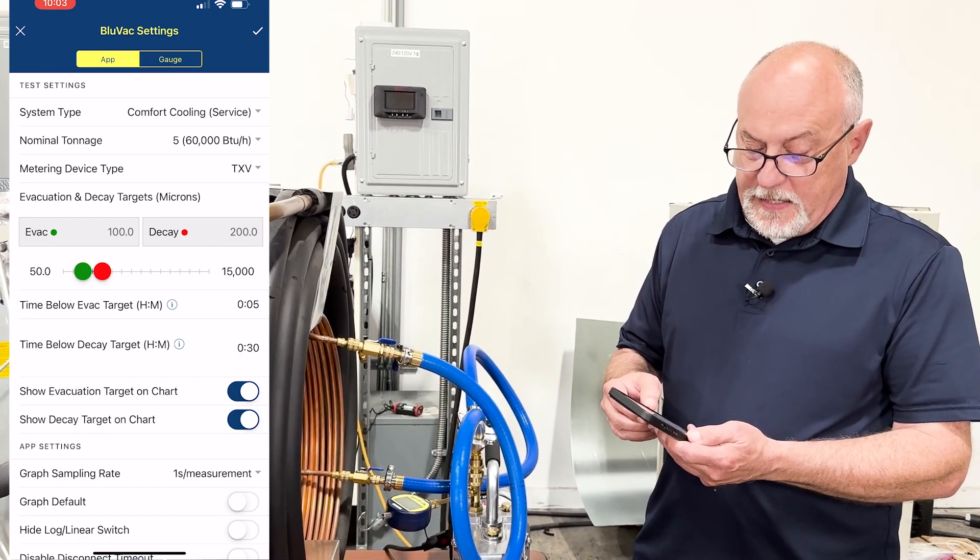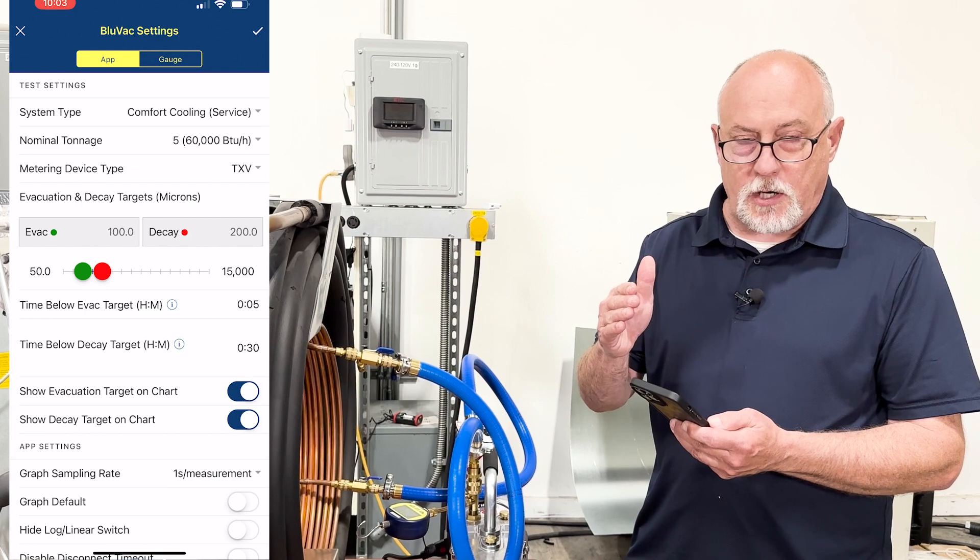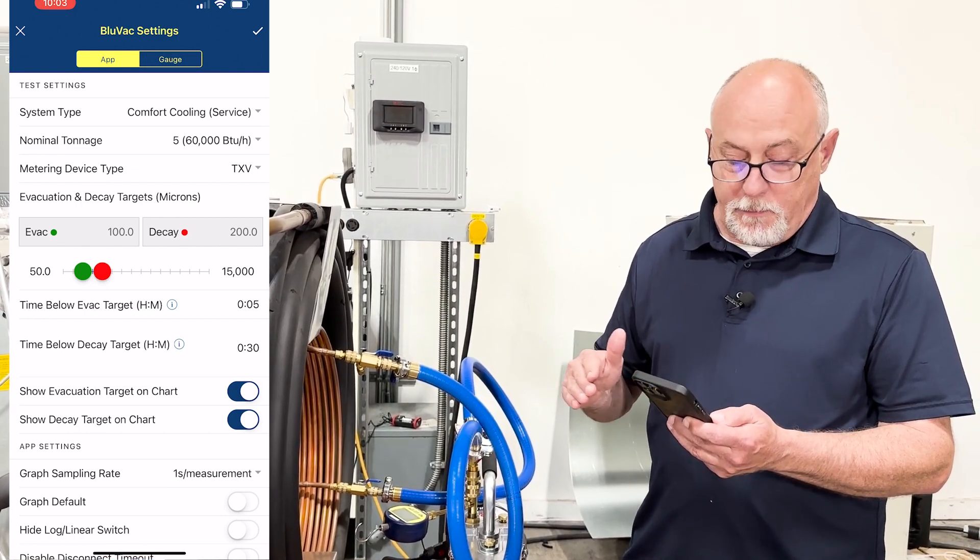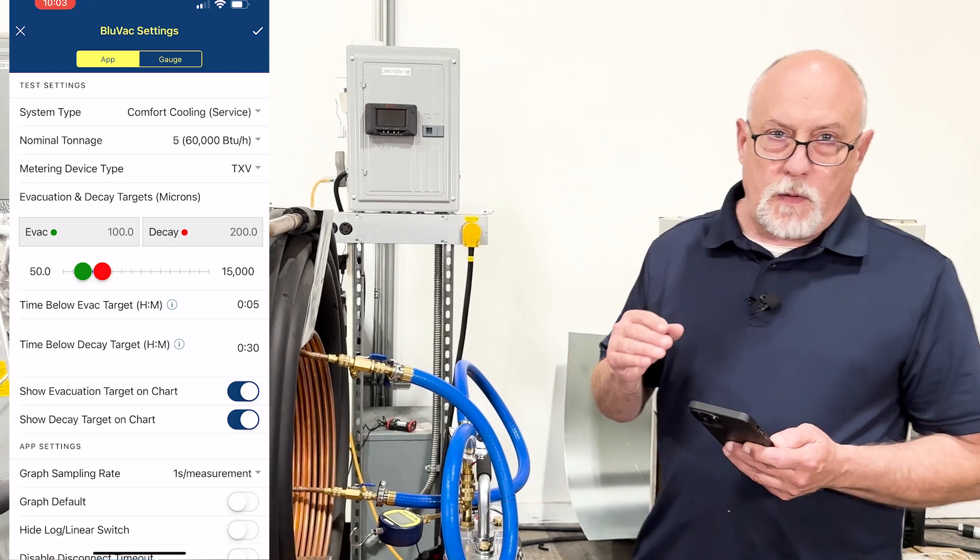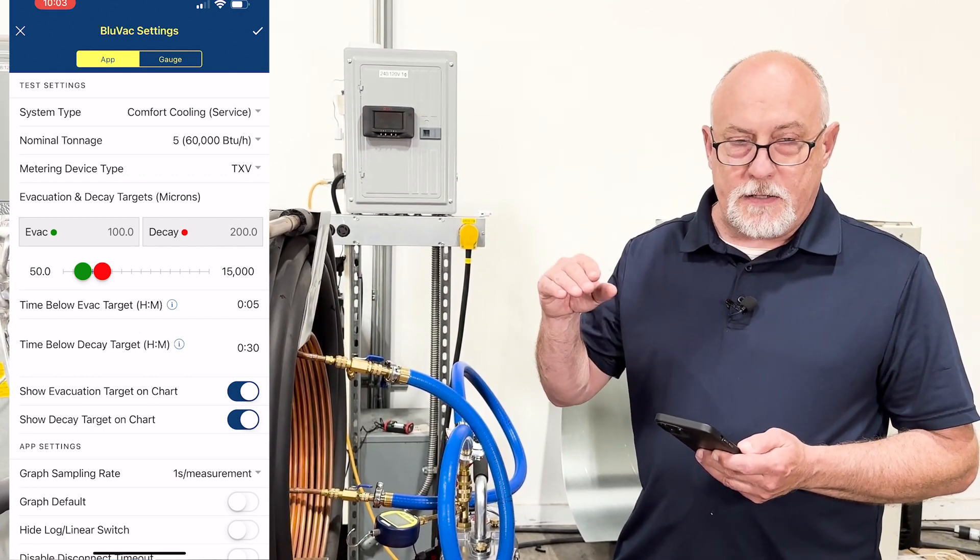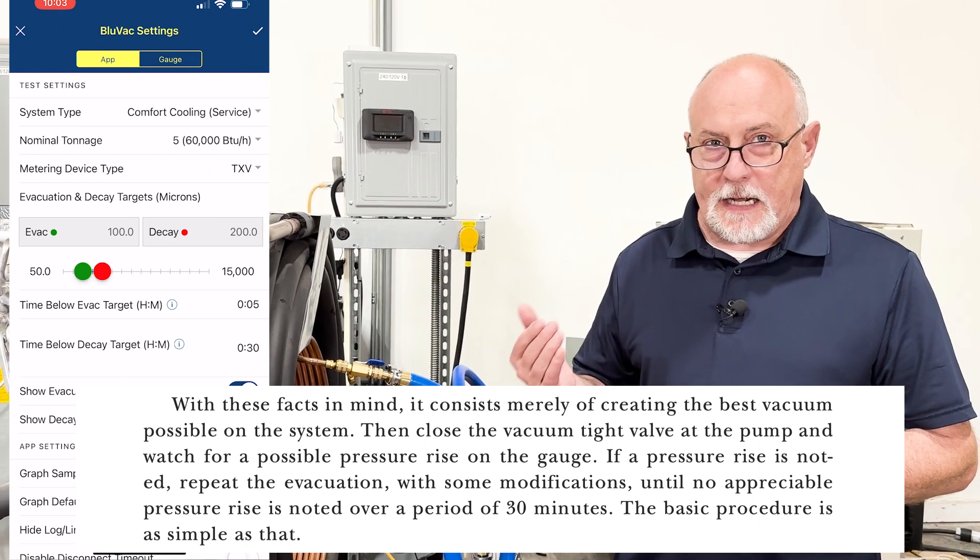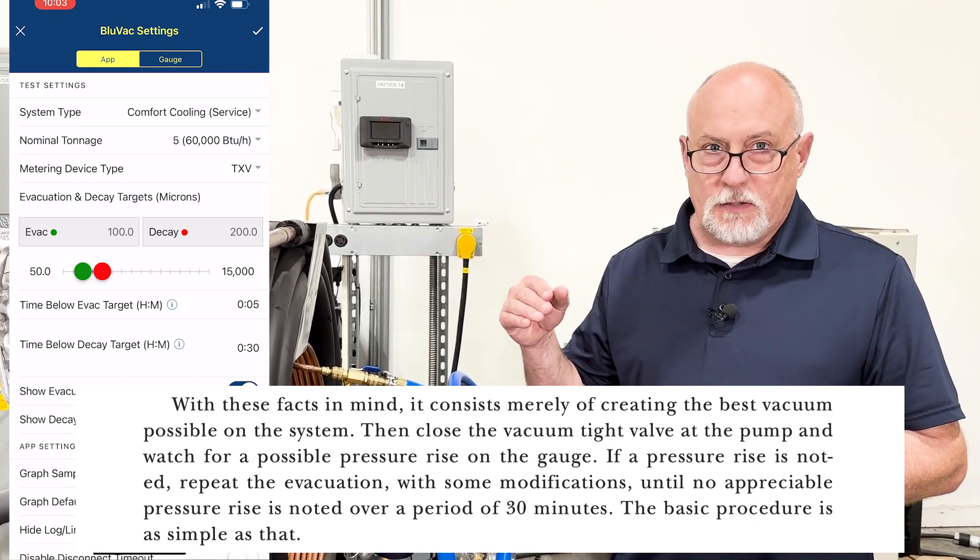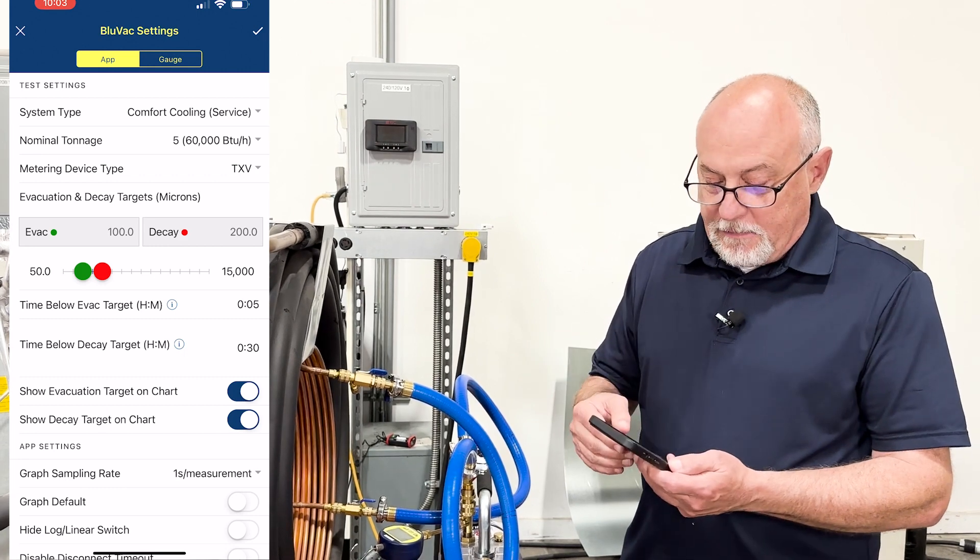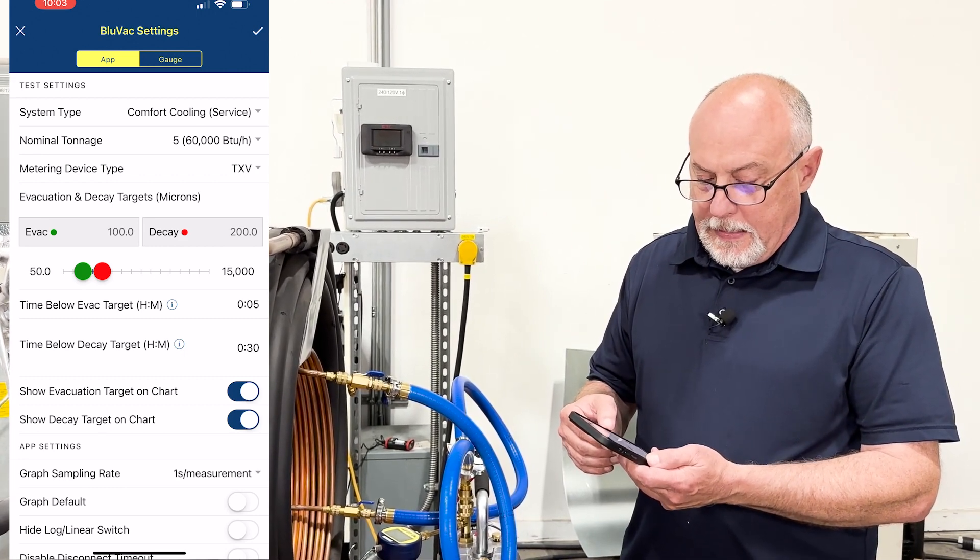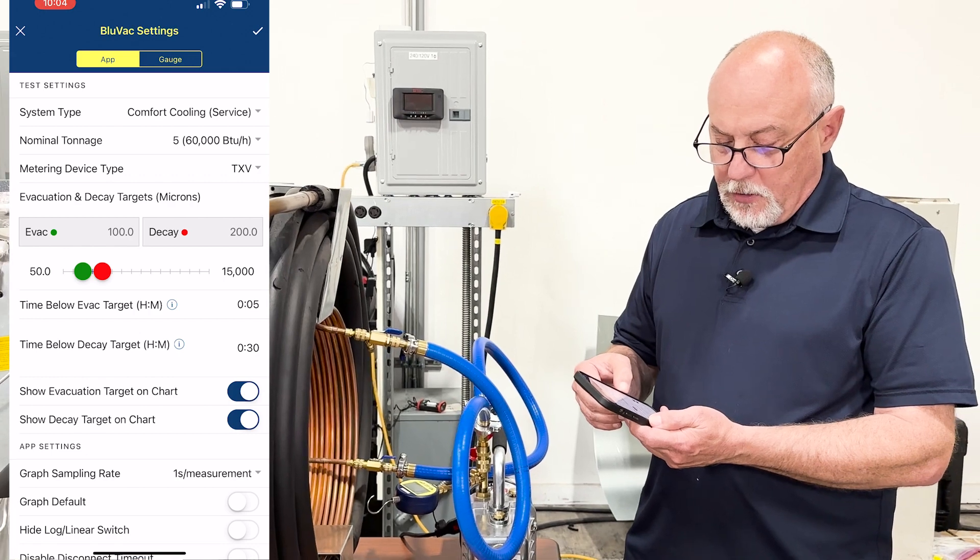Now there's a time below target setting, which I have set at five minutes. So that means when the graph is plotting down, when it hits the 100 micron target, we're going to hold below that for five minutes and I'll pull down below 100 microns. And then I have my time below decay target or my decay time set for 30 minutes. Now what we want to do with this is we want to make sure that there's no appreciable rise after 30 minutes. Back in the day, we'd actually have to wait 30 minutes. And the BluVac app has an algorithm in it that actually watches the rise over run and can tell you in about 30 seconds to a minute if you're going to pass that 30 minute decay test. So I have it set, again, 100 for the target and I have it set at 200 for the decay, show evacuation target on the chart, five minutes below the target and 30 minutes for the decay.